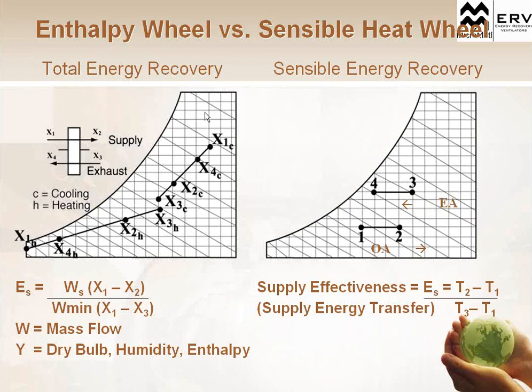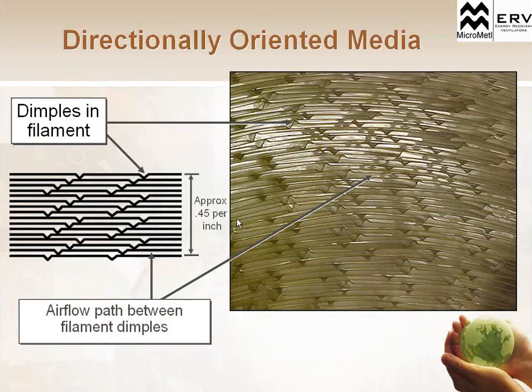A total energy recovery wheel, meaning sensible plus latent, or an enthalpy wheel, which is most ERVs and energy recovery, would mostly be an enthalpy wheel, where it's actually adjusting the temperature as well as the humidity. How do they do that? How does the wheel actually transfer humidity from a space? Well, these wheels themselves are made of a plastic polymer. So this is a plastic polymer. It's got little divots in here that allow airflow in between.